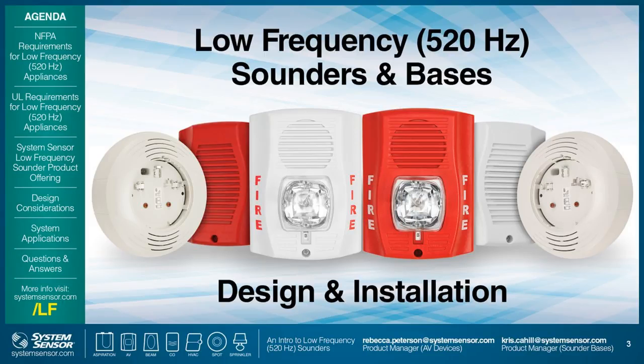Well, first I want to thank everyone for taking time out of your busy days to attend this webinar. The low frequency requirement is new and an important code that went into effect January 1st of 2014 and has impacted the sleeping space requirements within NFPA 72. While the tone is not that dramatic, the changes to the design of the products as well as the systems and the enforcement has been. These changes have impacted states and regions that are following the 2010 or the 2013 edition of NFPA 72. And coming January 1st of 2015, it will also impact those that follow the 2012 edition of NFPA 720.